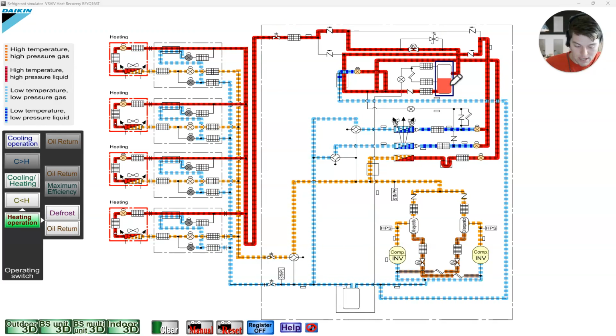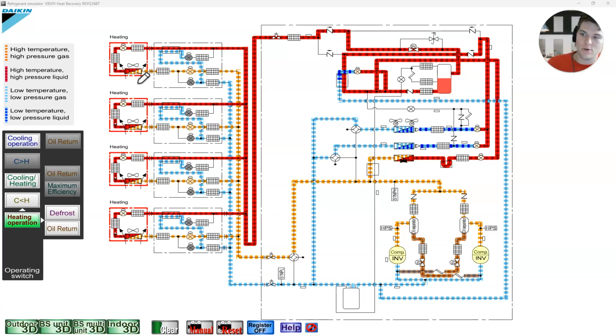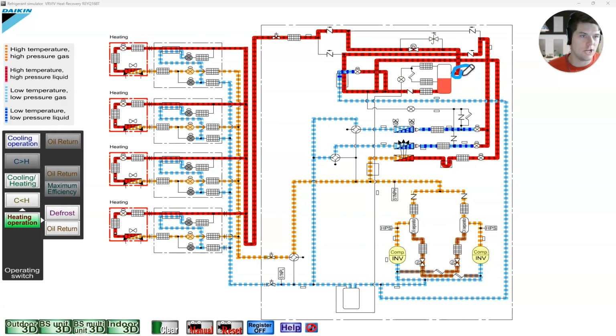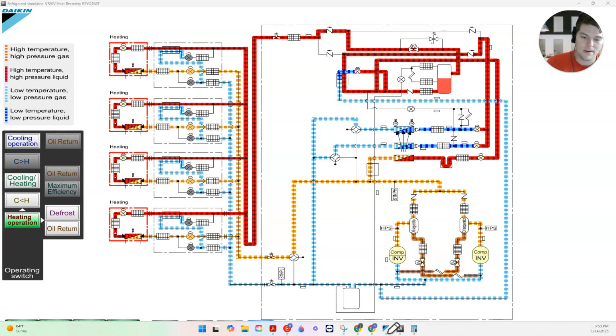Quality of subcooling means that we need to understand where is subcooling? Subcooling is at my indoor heat exchanger. It's where the liquid is created. We want to go to the spot where the liquid is created. Now, I'm not saying you can't check it here. It's great to check it here, right? But how do we fact check that? We fact check that by going to our indoor heat exchanger and saying, what is the quality of liquid leaving my heat exchanger? It went from a vapor to a liquid here. Let me check the quality. So let's check the quality.